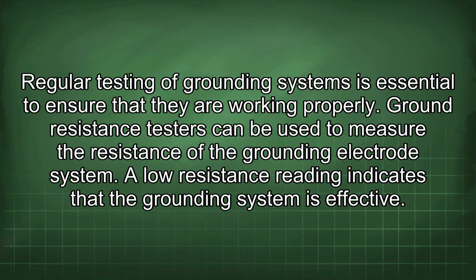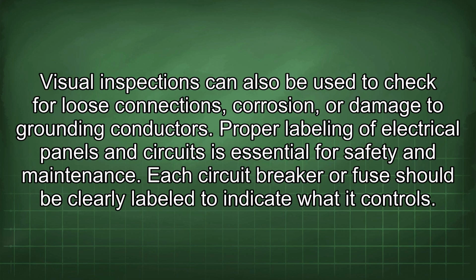Regular testing of grounding systems is essential to ensure that they are working properly. Ground resistance testers can be used to measure the resistance of the grounding electrode system. A low resistance reading indicates that the grounding system is effective. Visual inspections can also be used to check for loose connections, corrosion, or damage to grounding conductors.